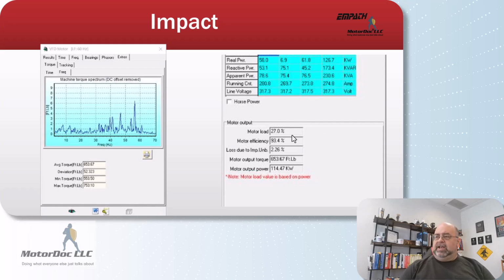So in any case, we get down to it. You can only have losses in the motor bearing between these values. And I had one of these companies, not very precise, try to tell me once that a three-quarter horsepower motor, well, let's just even round it up to a 1 horsepower motor, somehow produced 20,000 kilowatt hours in a year of losses from a slight problem with lubrication in a bearing.